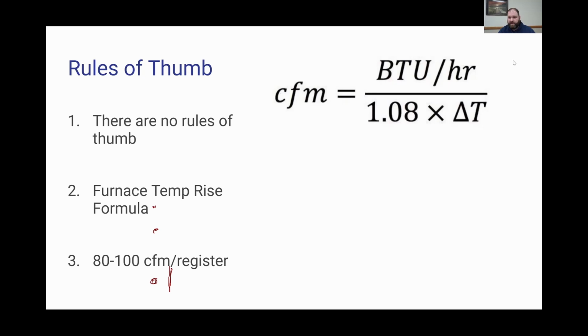I don't know if this is in your guys' way. Okay, so if you're seeing my screen, there's this formula over to the right-hand side. CFM, cubic feet per minute, is equal to the BTUs per hour of our equipment, so that's going to be our BTU rating, divided by 1.08, which is a constant, times our delta T, our change in temperature. Now, this is the sensible heat transfer formula, so it only works for that. We do a lot of furnaces, and we airflow check with furnaces a lot; that's our preferred method. All you have to do is put the furnace in heat mode, take the return air reading, take the supply air reading. The difference in those becomes your delta T, and your furnace will have a BTU per hour rating on it. And that's going to generate a CFM that will be in the ballpark.